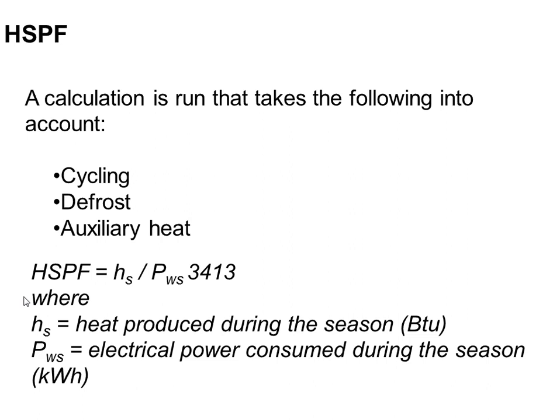If my outdoor unit now becomes my evaporator coil, my indoor unit's my condenser. Well, if my evaporator's outside, that's where the condensation is going to occur in terms of air on the coil. And if it's freezing outside, below 32, that condensation could freeze or frost the coil, so we need to defrost it. The way we defrost the heat pump is by running it as an air conditioner again temporarily. So for whatever, 3 minutes or so, we're running in air conditioning mode and basically using the heat from inside your house to thaw out the outdoor coil, and then we switch back to heating mode. Well, that solves our defrost problem. It does have a little bit of an energy penalty, so the HSPF number takes that penalty into account.